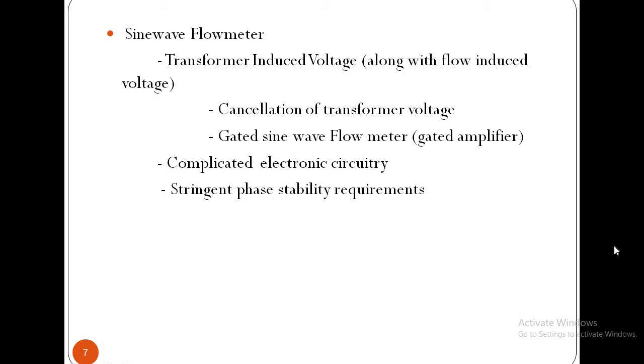First is a sine wave flow meter. In a sine wave flow meter, the probe magnet is energized with a sine wave, and consequently the induced voltage will also be sinusoidal in nature. The major problem encountered with the sinusoidal type of magnetic field is that the blood vessel and the fluid contained in it act as a secondary coil of the transformer when the probe magnet is excited.